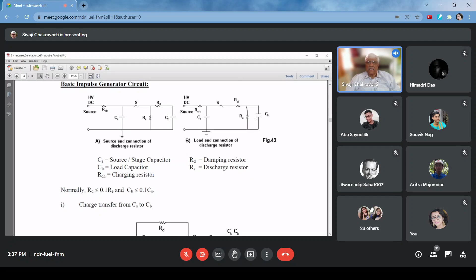Now RD can be after RE on the load side or before RE on the source side. Depending on that, the circuit in figure A is called the source end connection of RE, since RE is connected on the source end, and circuit B is called the load end connection, where RE is connected on the load end. The capacitor CB is not the capacitor of the tested object, it is a capacitor placed in the generator, called the load capacitor.